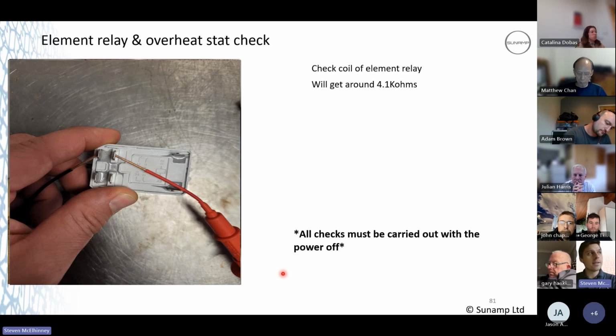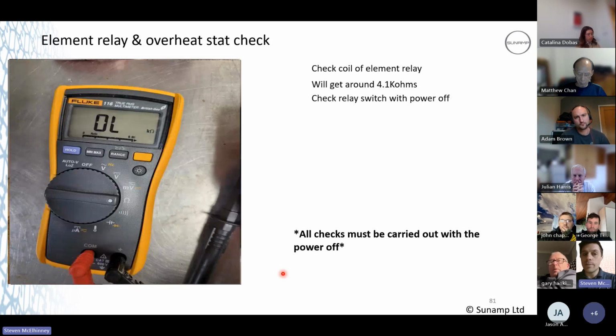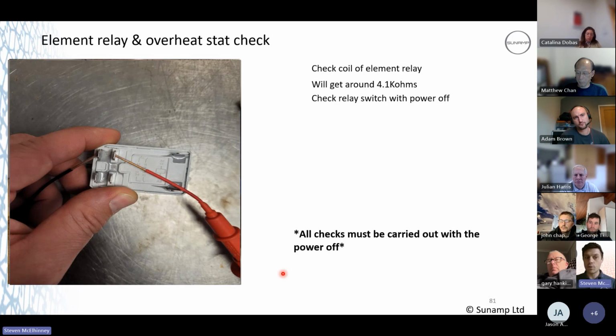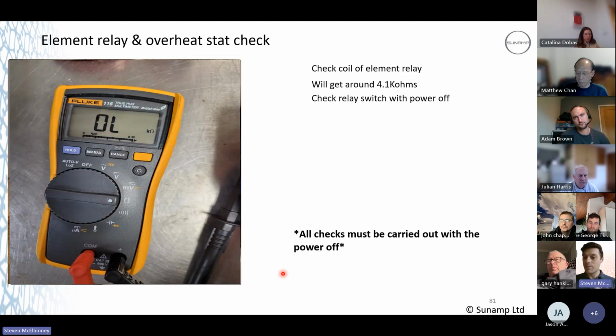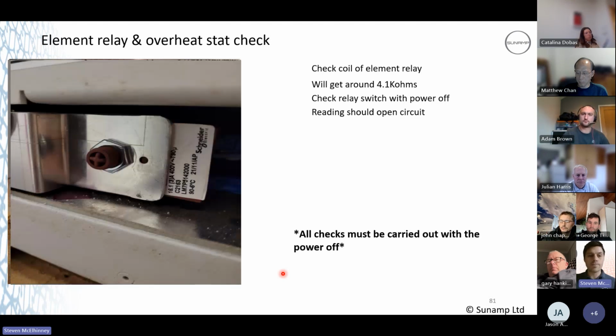If you're getting intermittent overheating, with temperature sensors pushed fully home, you could be getting a sticking relay. So with the power off, you should be getting open circuit, but if you're having that scenario with intermittent overheating, what we do is allow the battery to charge a little bit, allow some heat to be generated within that relay, and then do the same test. And if you're getting any form of resistance across those 2 contacts or 4 contacts, then you know that there's a sticking relay, or it's allowing some form of electricity through if it's a bit sticky. It should read open circuit.